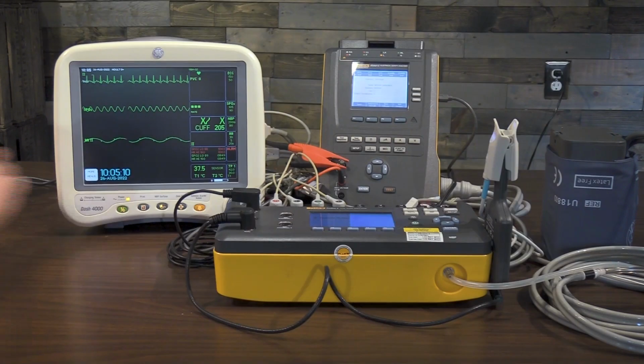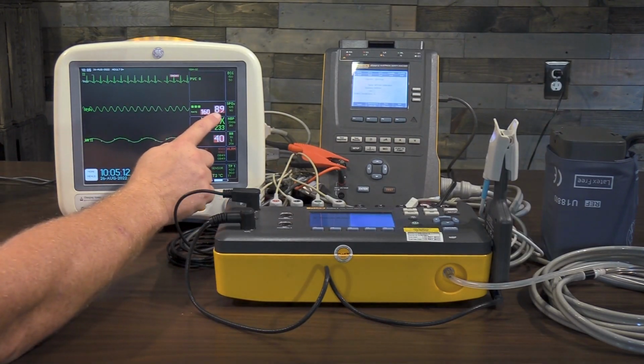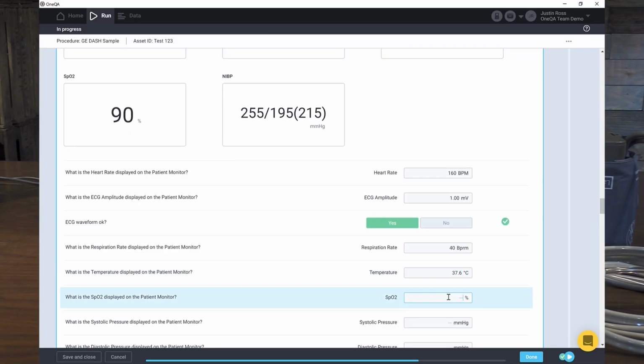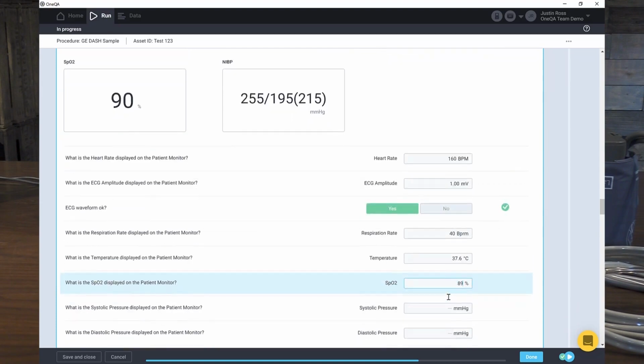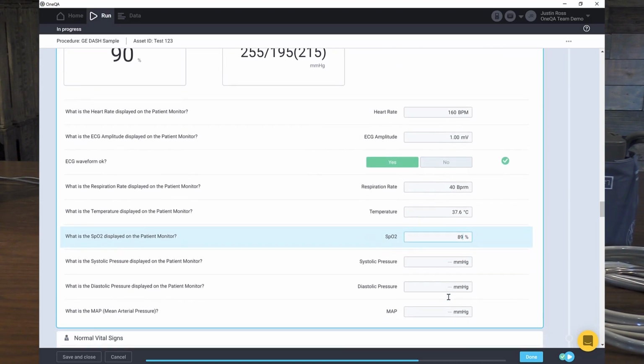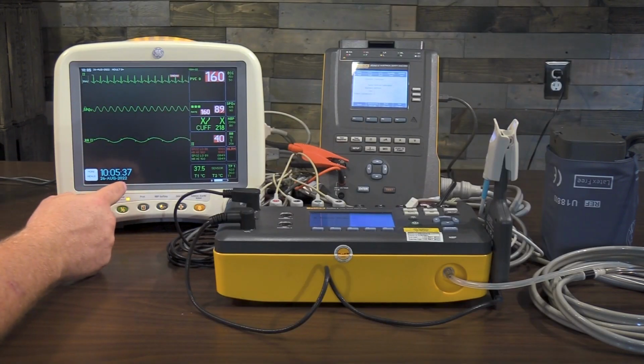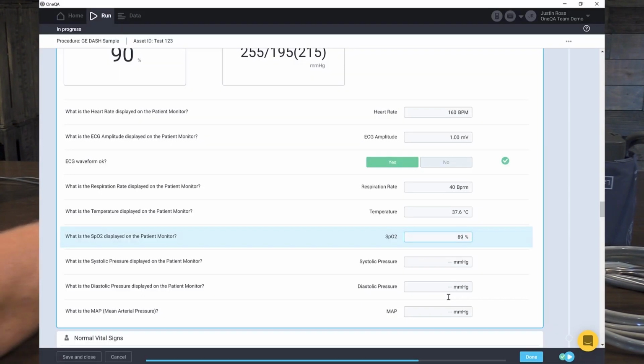SpO2 we have set at 90. We are reading 89. All right, now our blood pressures. This is just to verify that we can take a diastolic blood pressure. Since we're over pressure, it's going to take a little bit for it to catch it the first time. And you could hear it ran through once. It's running it through the second time. And there we have a capture of 275 over 190.